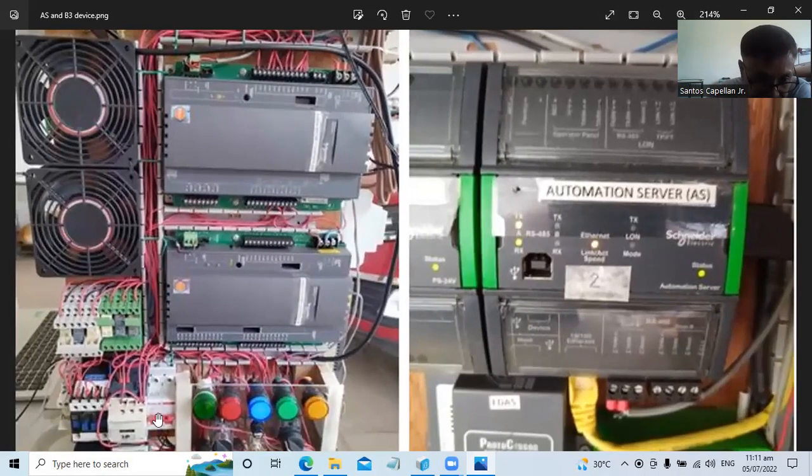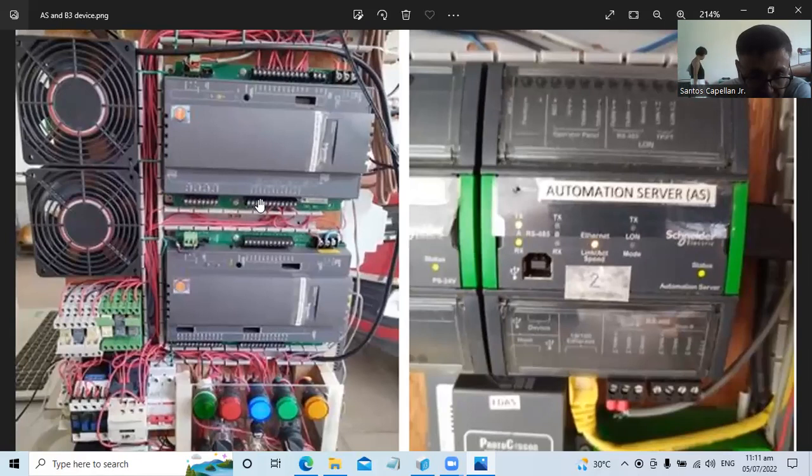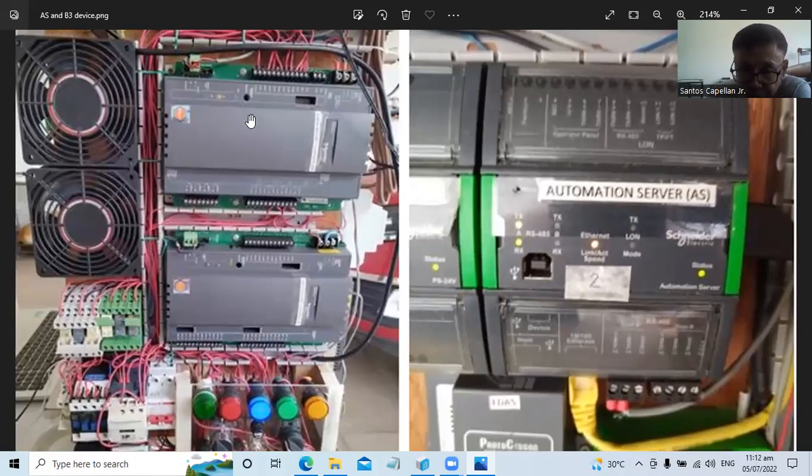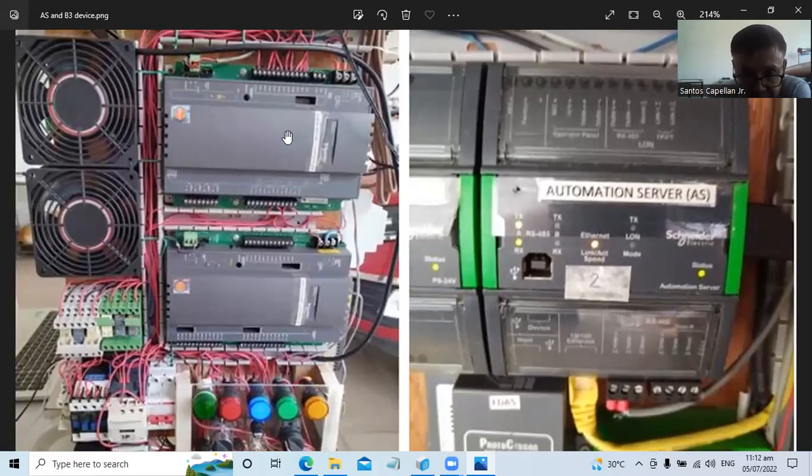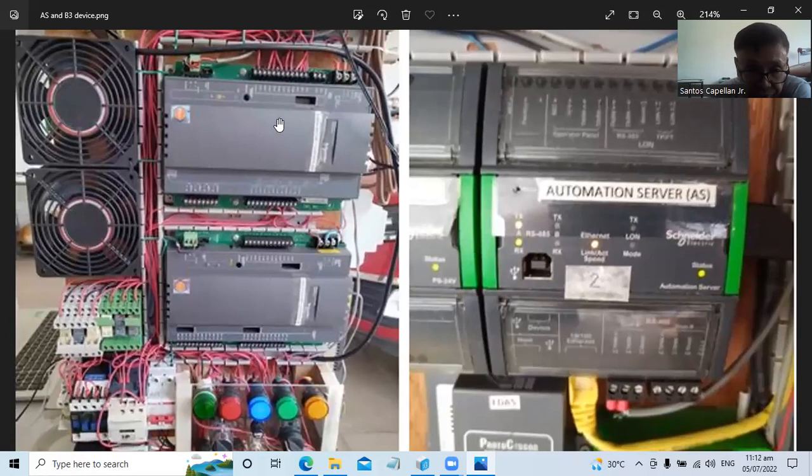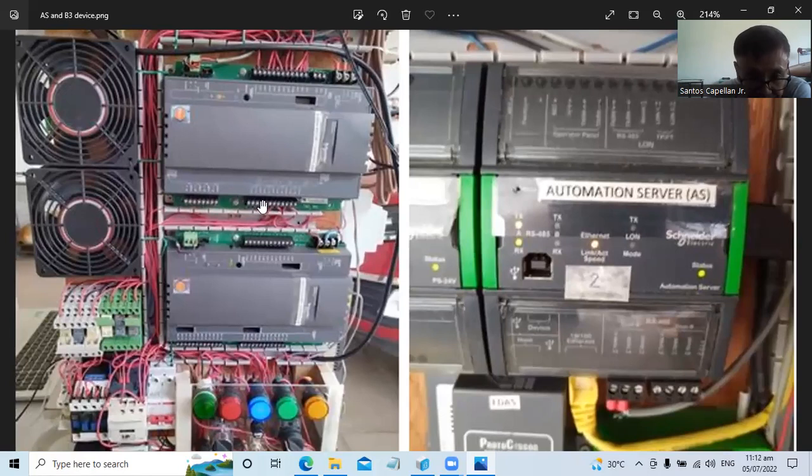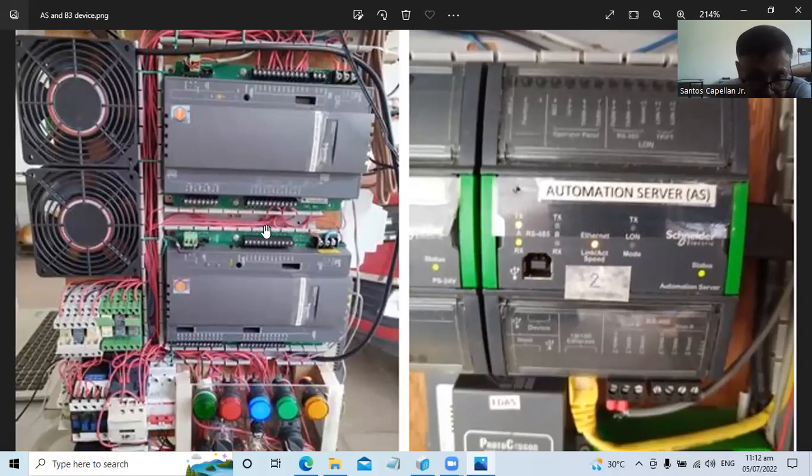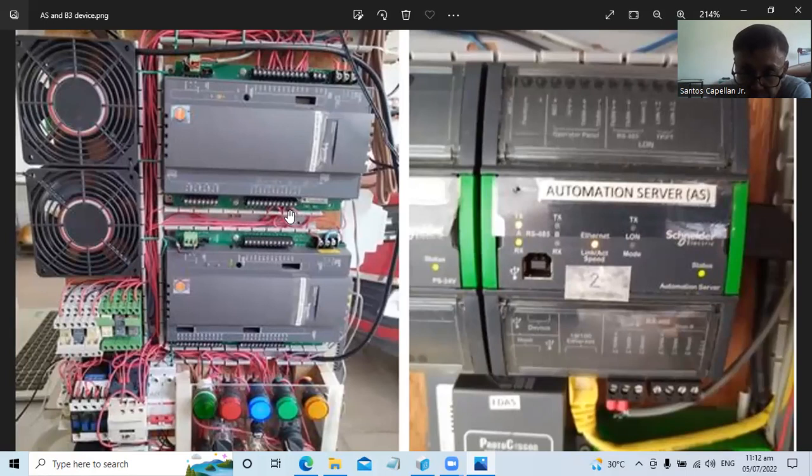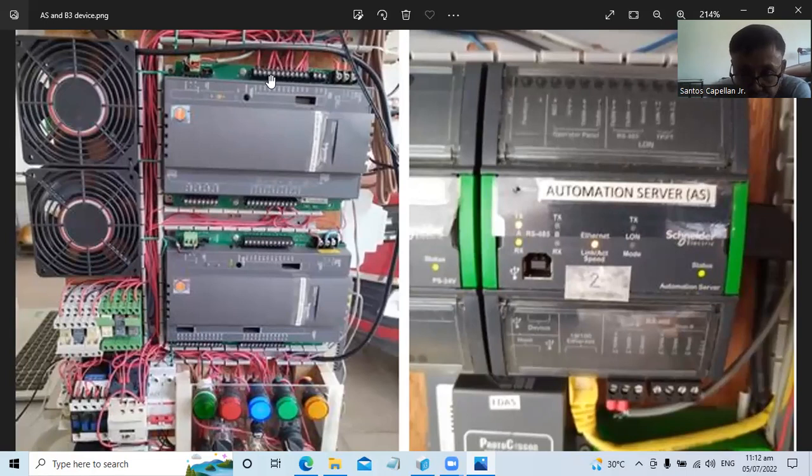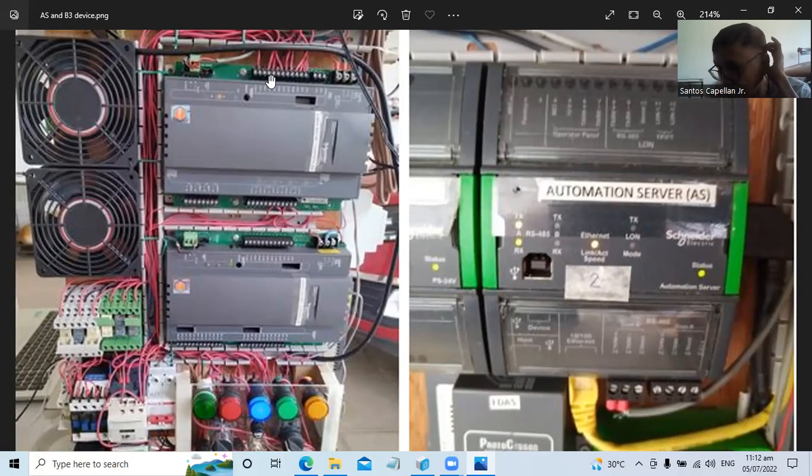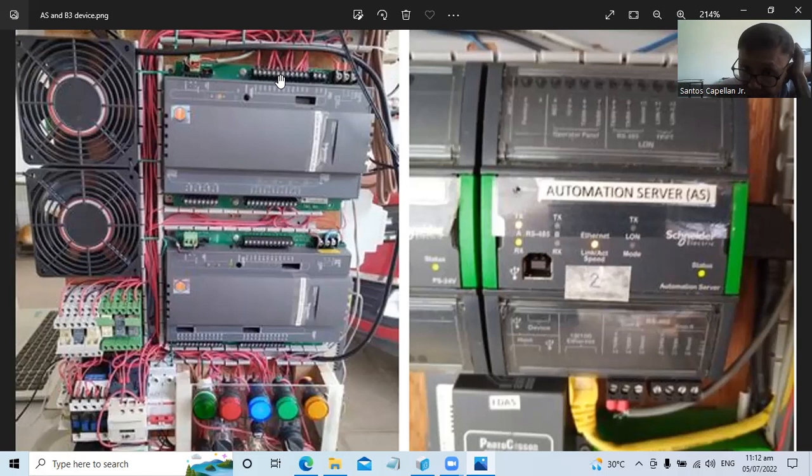For these two simple exhaust fans, I was able to use only this controller. This B3804 has eight universal inputs and four digital outputs. Since this is only two fans, I only use two digital outputs, output channel one and two.